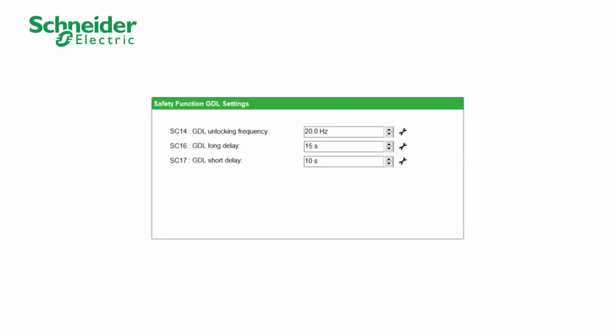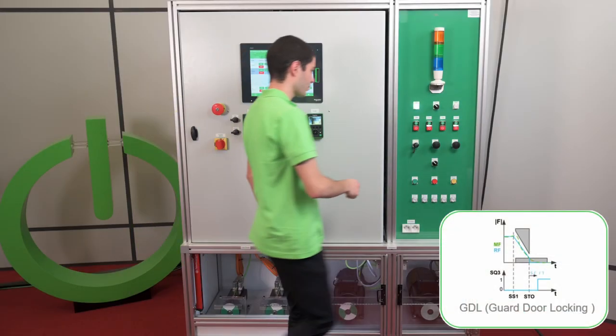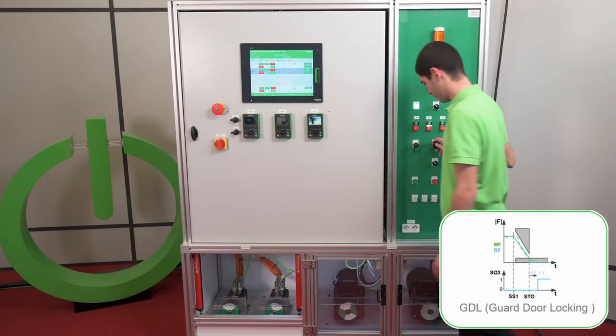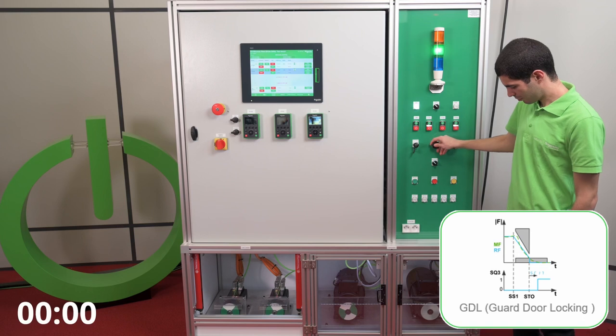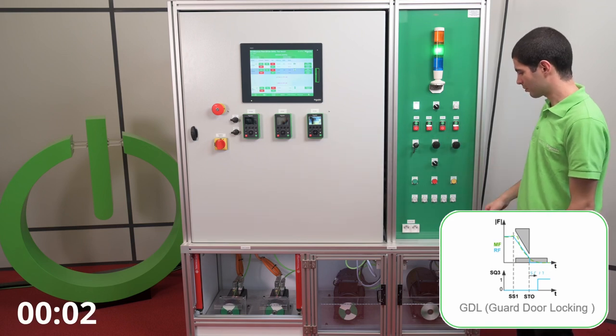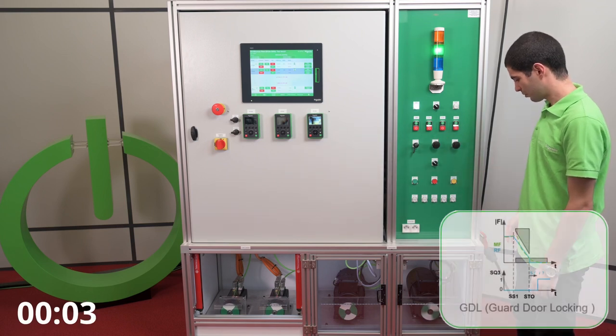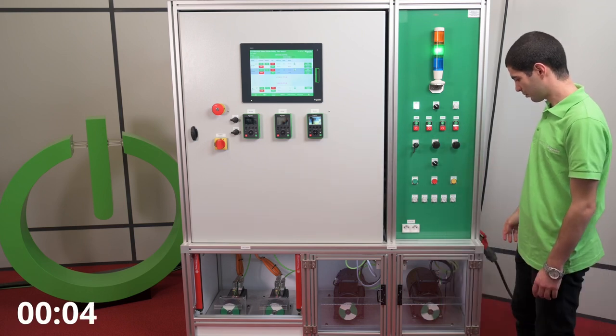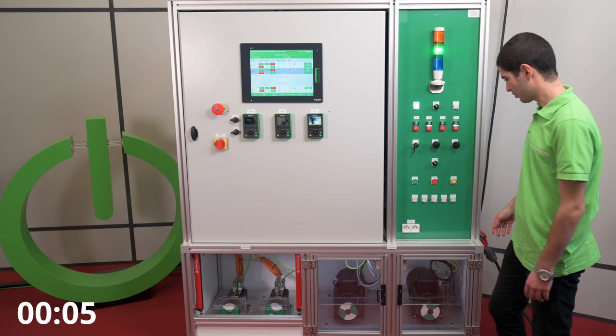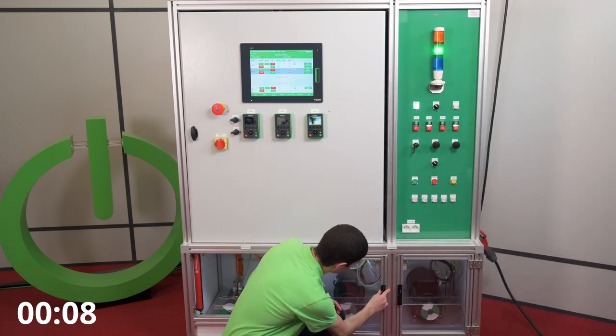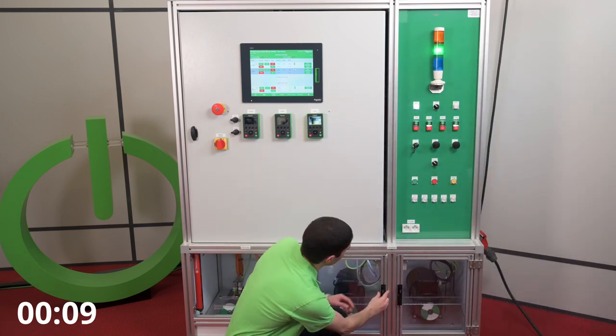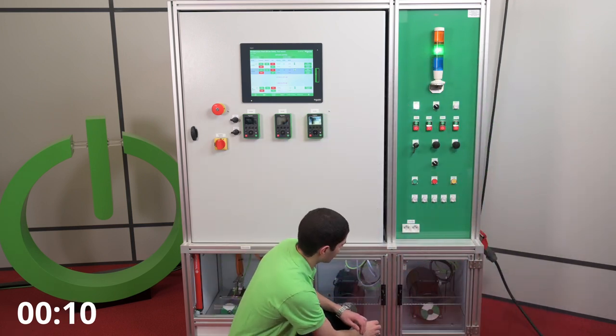We configured GDL using SoMove. While the motor is running, we cannot open the door. We give a stop order — the motor stops, but we cannot open the door for a configurable delay. After that configurable delay, we can open the door.